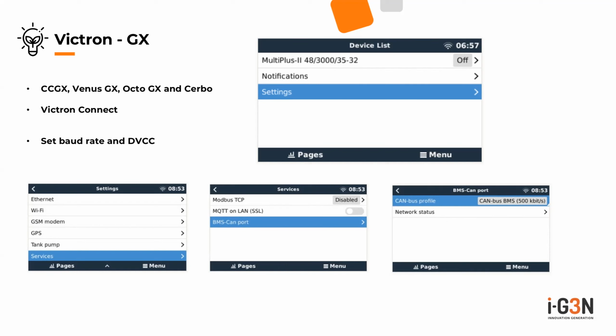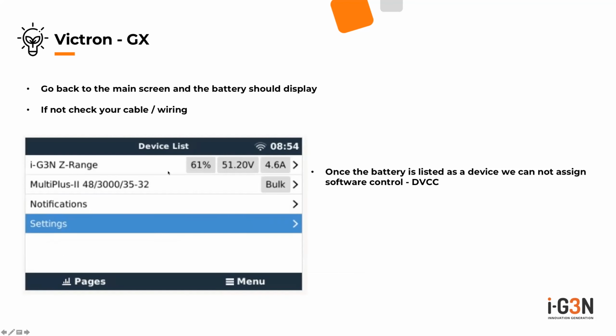Once that's done, we move on to DVCC. You'll see your product now part of the device list at the top - go back to the main menu and you'll see your battery displaying there. If it doesn't display, it means there's something wrong in the cabling - double check your cable or wiring until the battery registers as a device on the list. Once that's done, you can move forward with your DVCC settings.